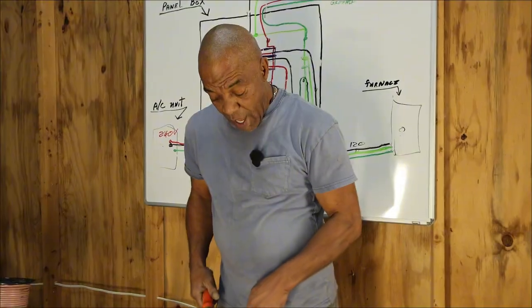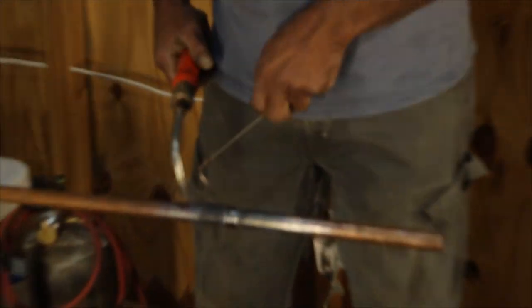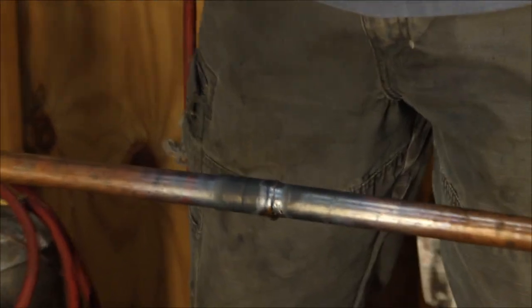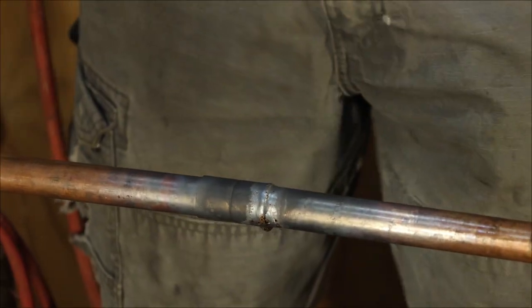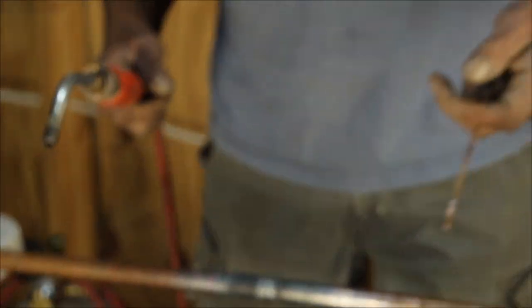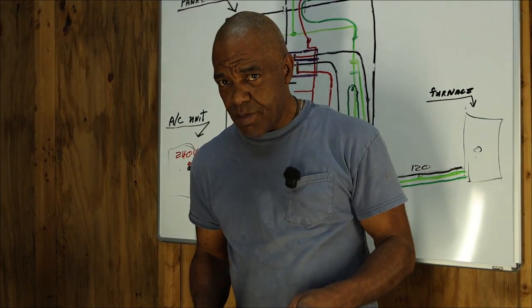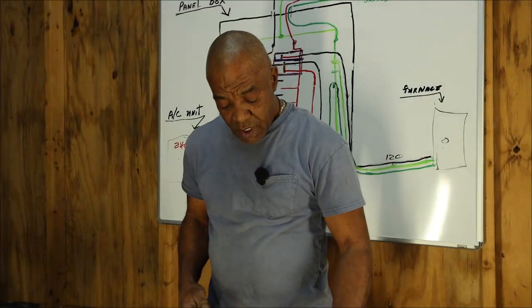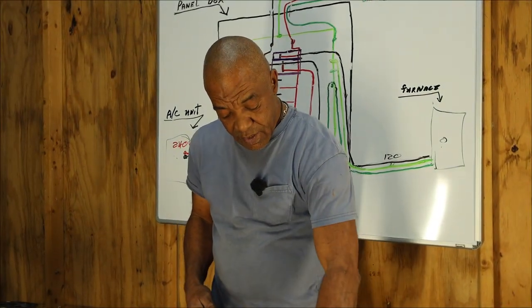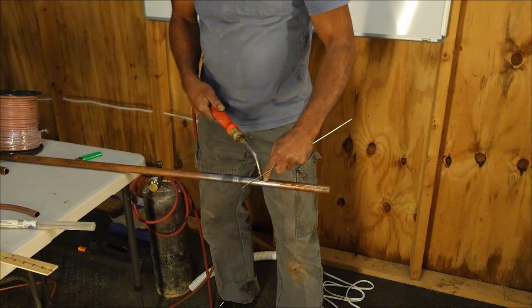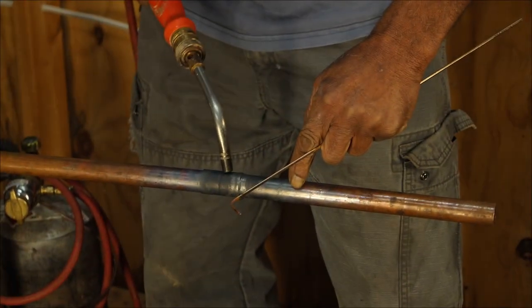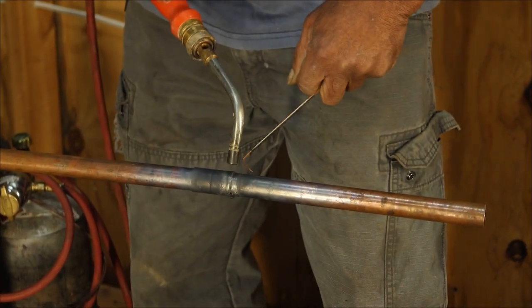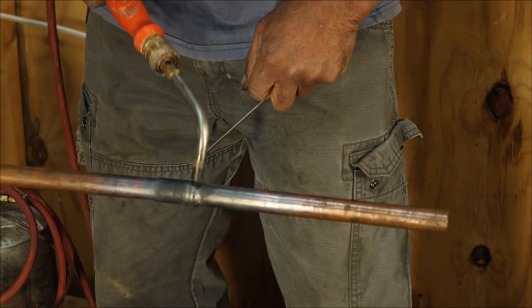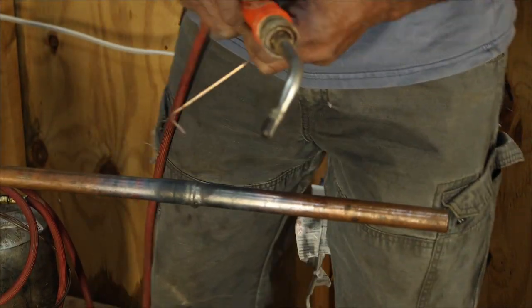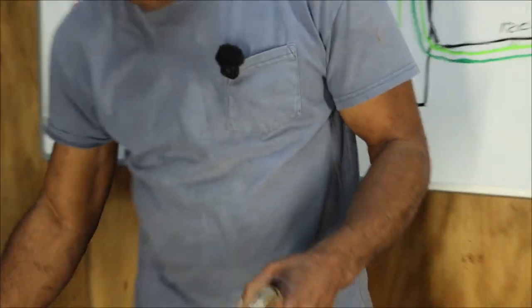Also, I now have to connect the other side. So what I would typically do, because I don't want callbacks, I want to make sure my job is done to the best of my ability, is put a wet rag back here about 3 inches away from where I'm working to ensure that I don't re-melt this connection. But you can do it without the wet rag, but here we go.